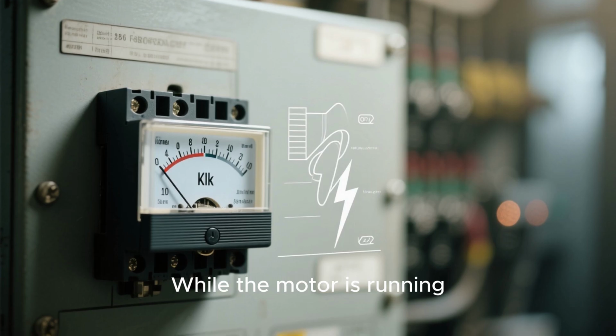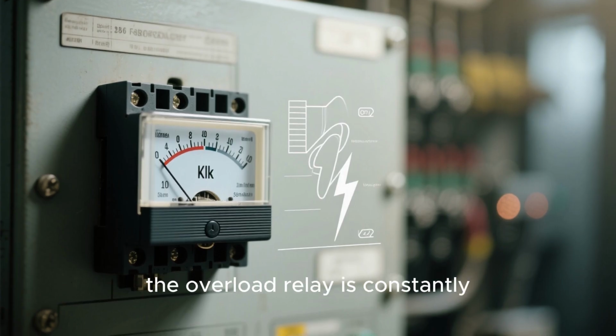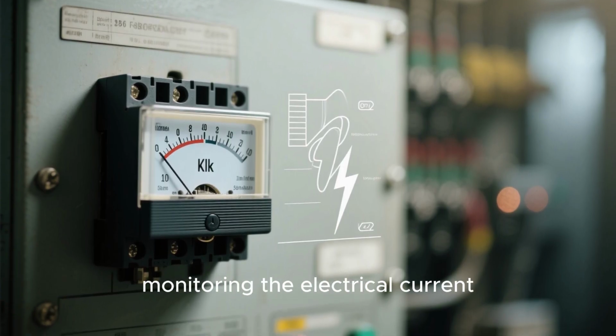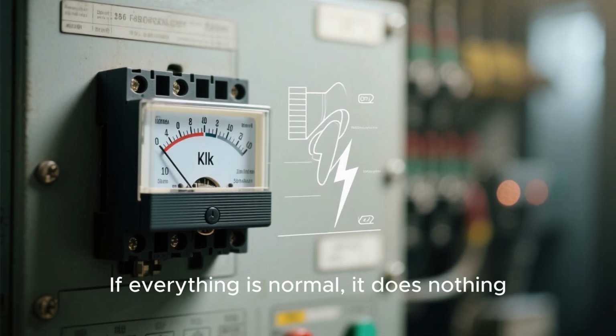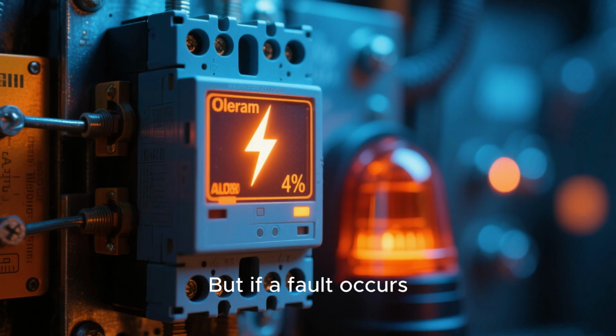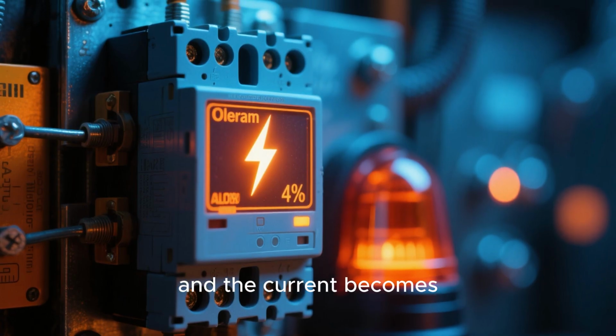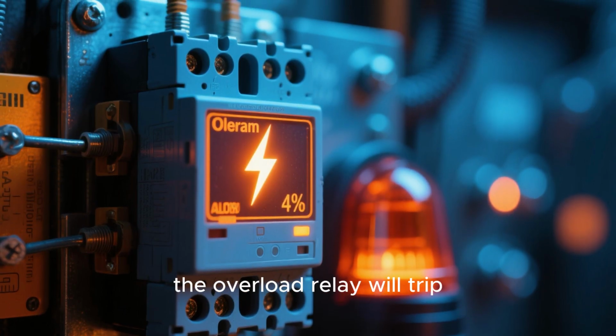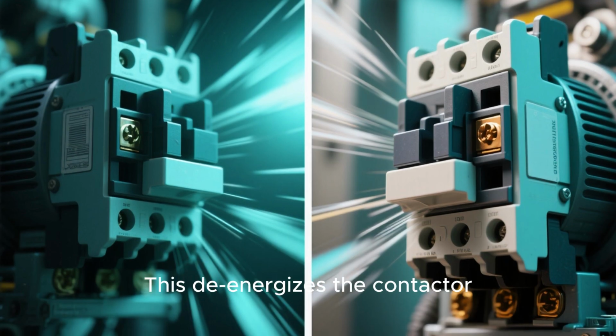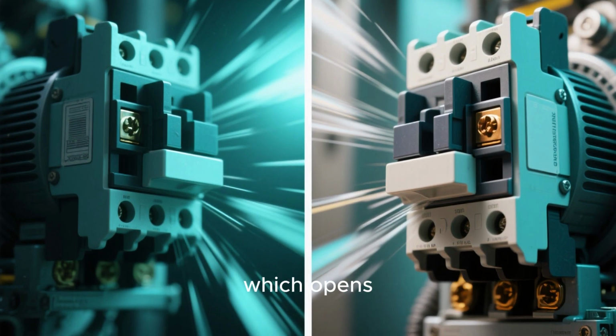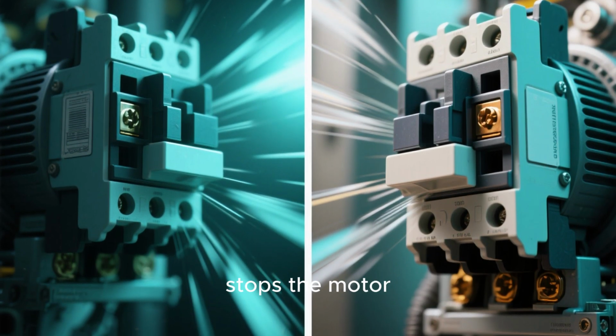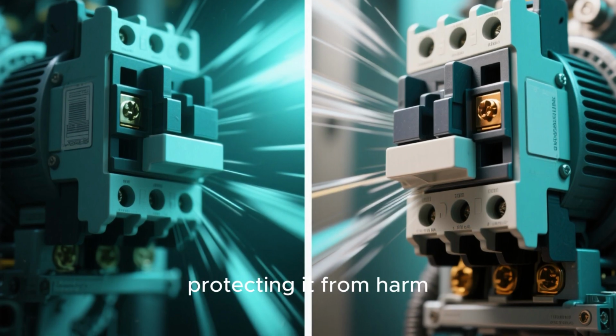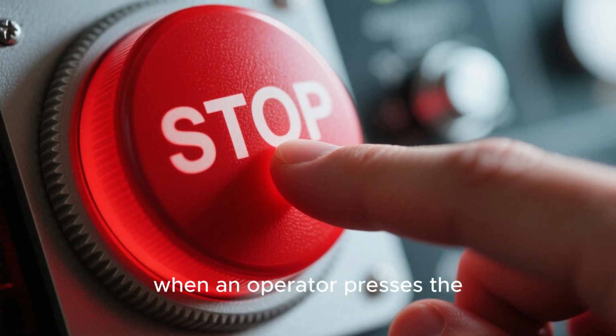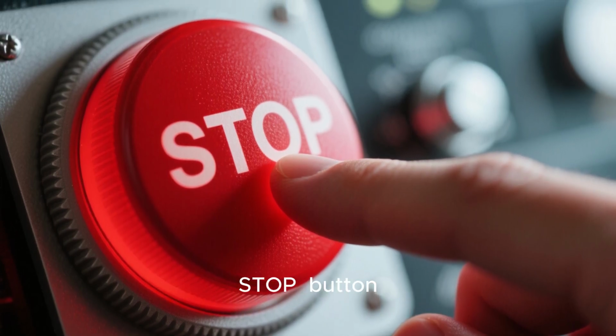belt. While the motor is running, the overload relay is constantly monitoring the electrical current. If everything is normal, it does nothing. But if a fault occurs and the current becomes dangerously high, the overload relay will trip. This de-energizes the contactor, which opens its contacts and immediately stops the motor, protecting it from harm. The motor also stops when an operator presses the stop button.